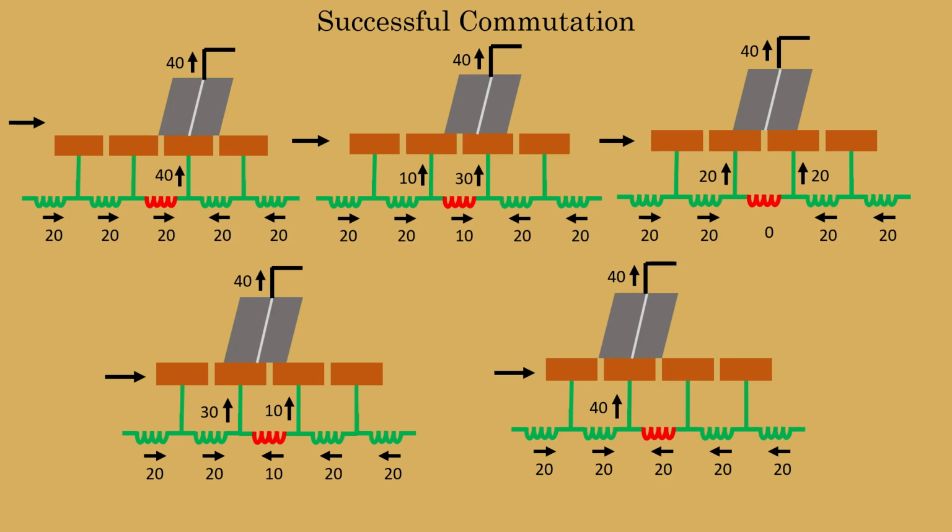The brushes used in industrial motors are graphite and electrographite materials. These materials are good conductors, however, they do present some resistance to current flow due to their resistive nature, and this is a good thing. Resistive brushes aid in the process of commutation.